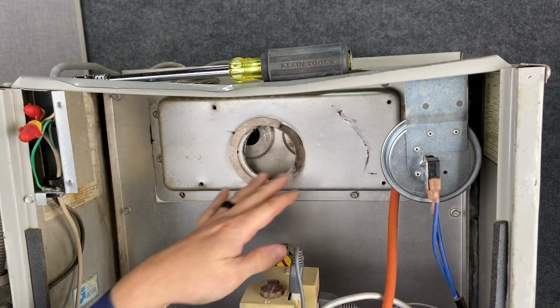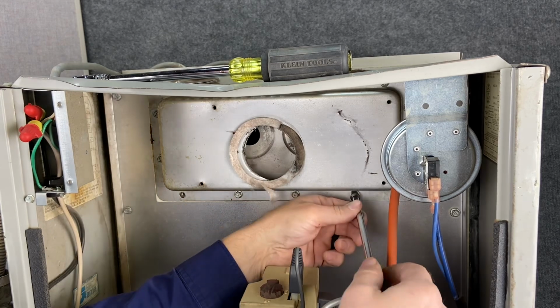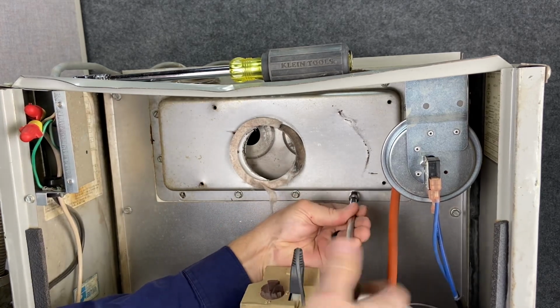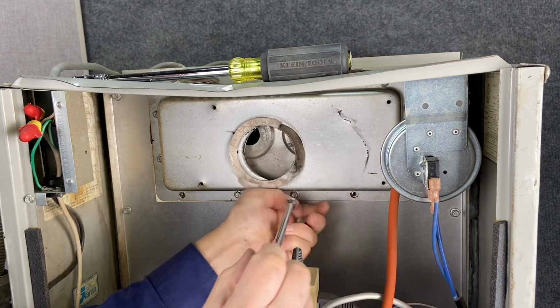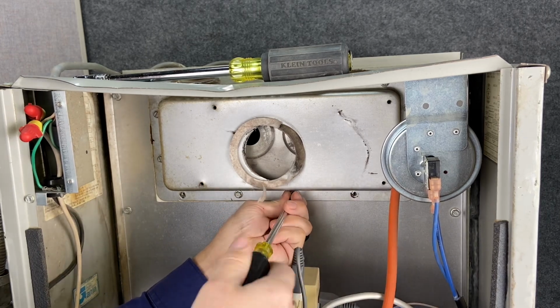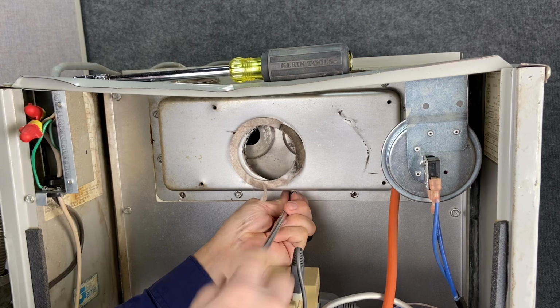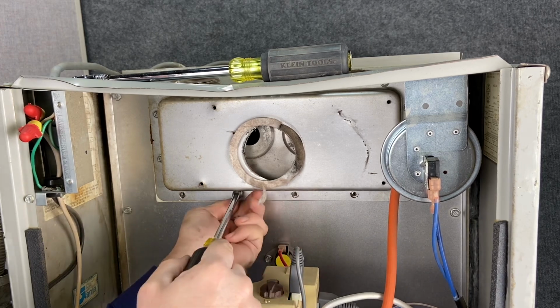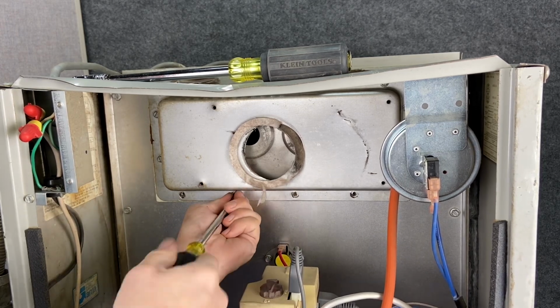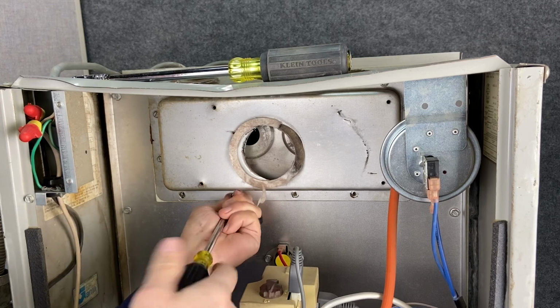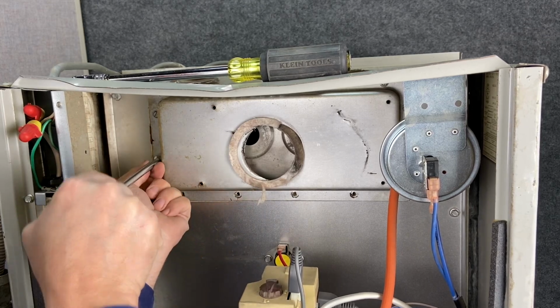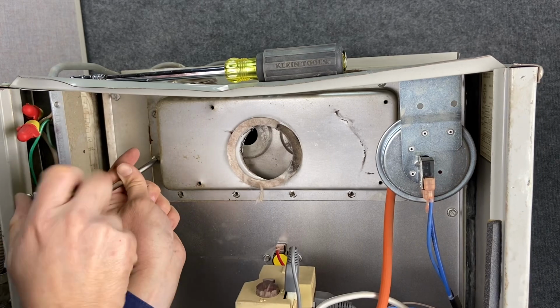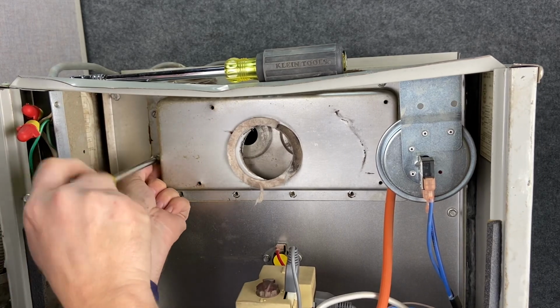This component here has its own name as well. It is the collector, the draft hood collector. So all of the individual furnace components or furnace heat exchangers are going to collect together in this one little chamber. Then the inducer fan is able to pull a draft equally between all of these heat exchangers. So once we pull this off, you can see exactly what it looks like behind it and the individual heat exchangers.